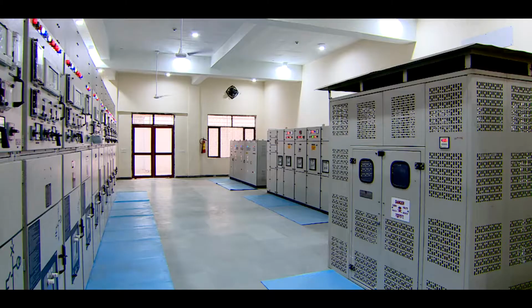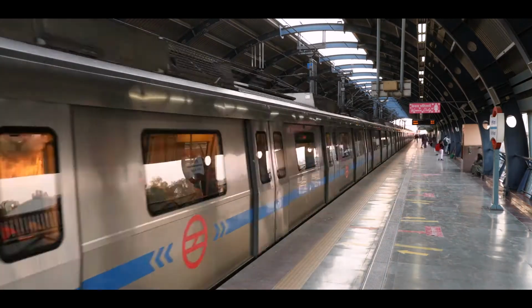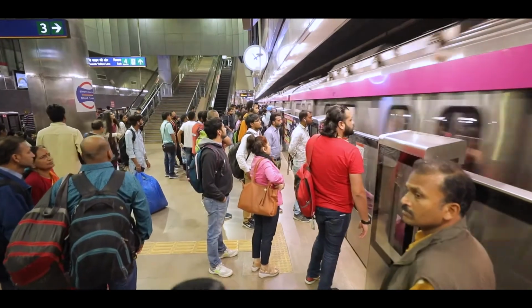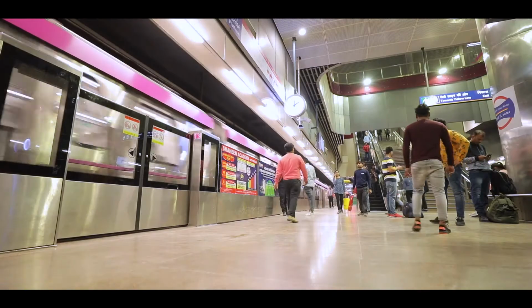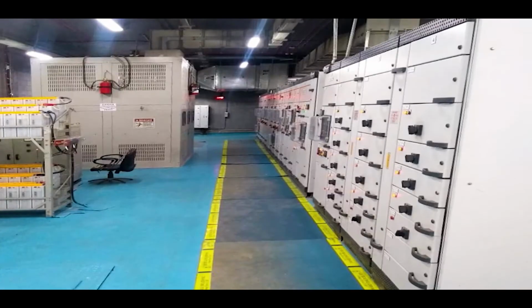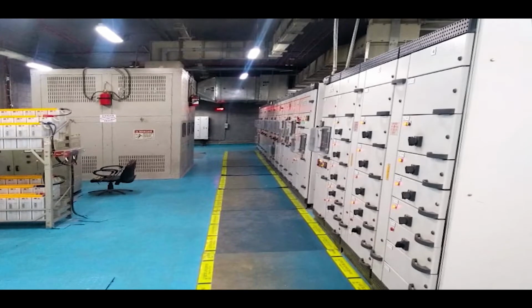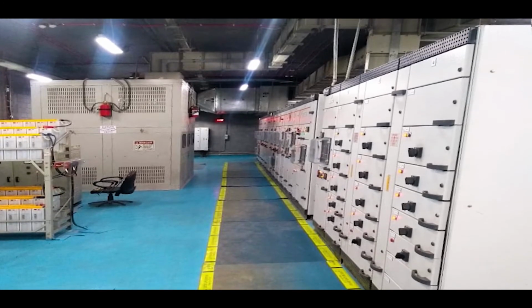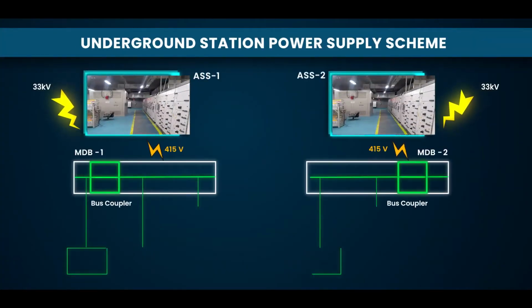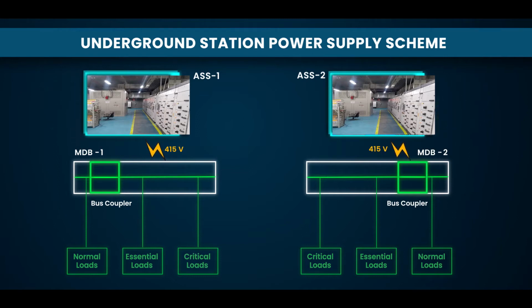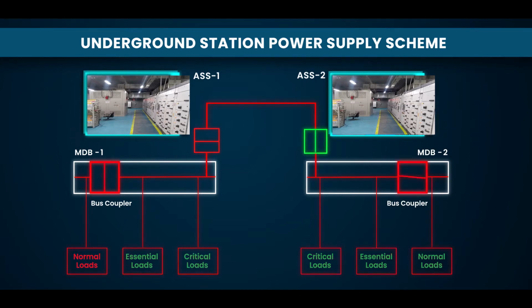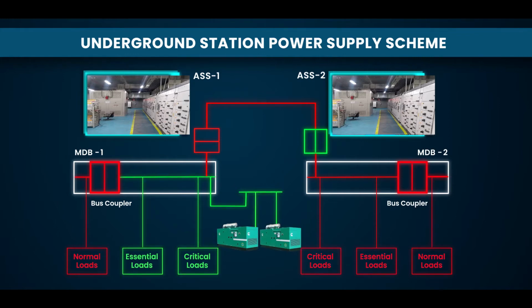Elevated stations are provided with one ASS and one main distribution board which distributes power to all the utilities in the entire station. Underground stations are divided into two halves as the quantum of electrical loads is more. Each half is provided with an auxiliary substation housing an auxiliary transformer and a main distribution board. Each ASS distributes power to utilities in its respective half. In case of failure of both sources of 33 kV power supply, essential and critical loads are provided backup supply using diesel generator sets. In addition, critical loads also have backup of battery-backed UPS.